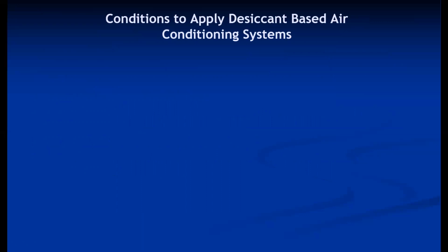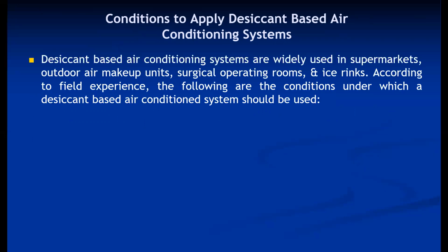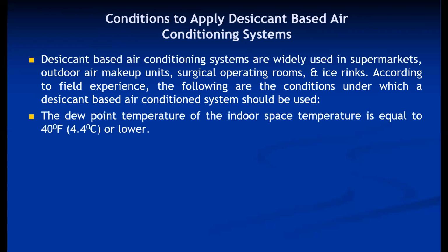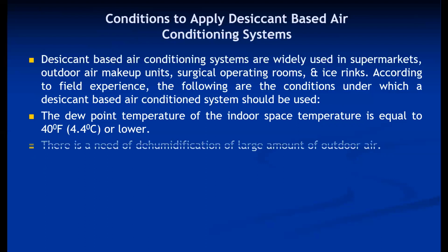These desiccant-based air conditioning systems are generally suitable for certain applications. They are mainly used in supermarkets, outdoor air makeup units, surgical operating rooms where 100% fresh air is used, and ice rinks. According to field experience, the following are the conditions under which a desiccant-based air conditioning system should be used. Generally, it is recommended if the dew point requirement is less than 4 degrees Celsius.